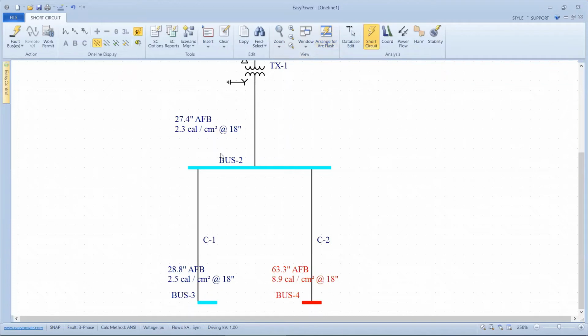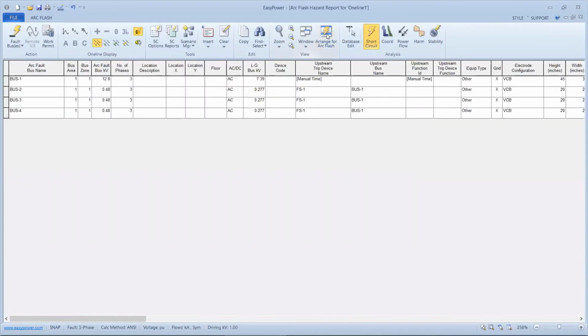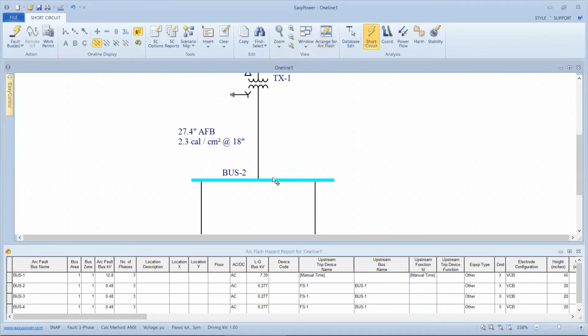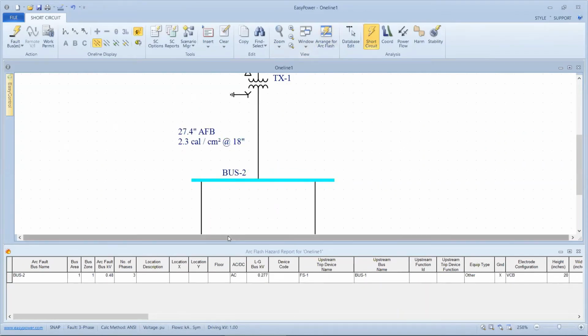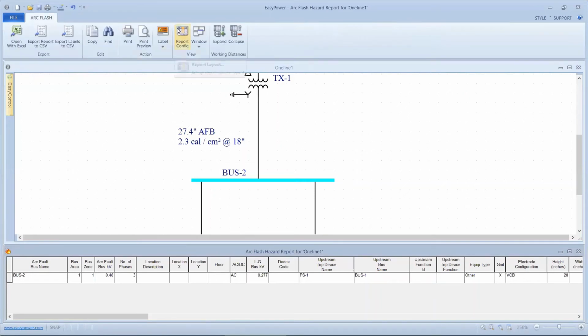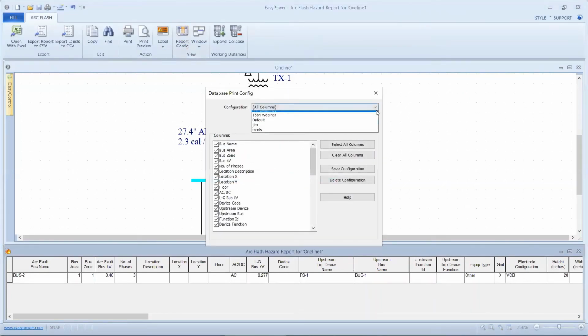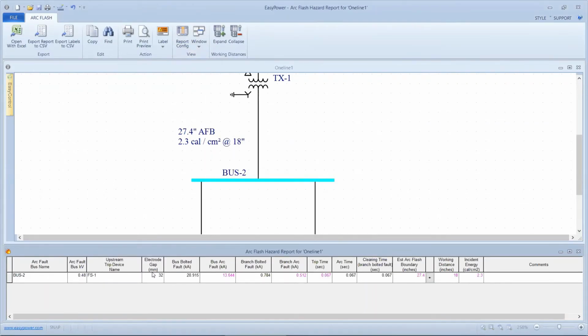Because at any point you're doing an analysis, you need to know if the calculations are correct. So the utility that we offer to do that is called the Arrange for Arc Flash icon, which allows me to look at the one-line diagram and the way the calculations are being made in the tool. And so if we highlight the transformer secondary, we see it's a 480 volt bus. The fuse is a protective device. The air gap, let me modify my report. The air gap is 32 millimeters.